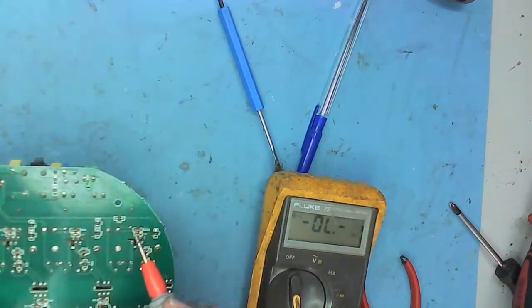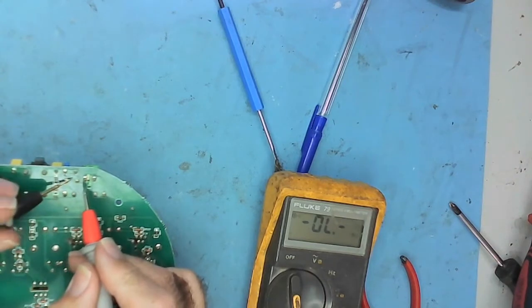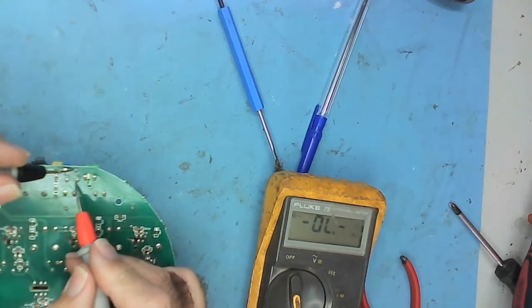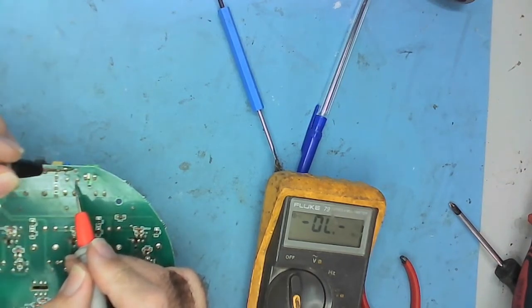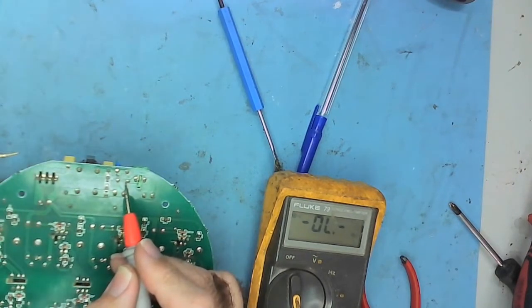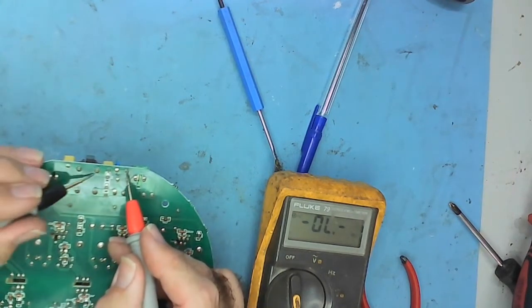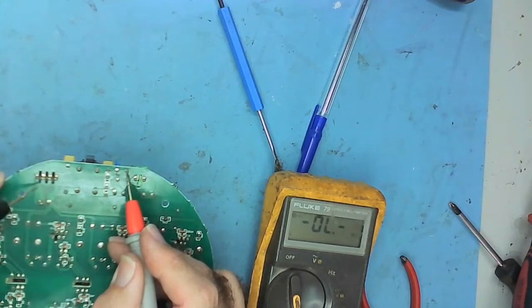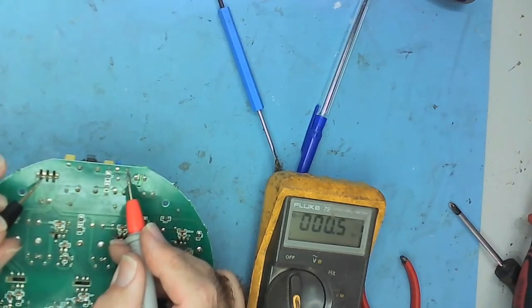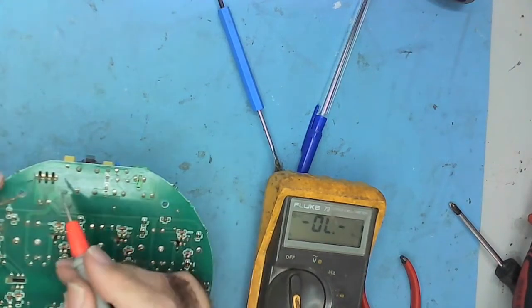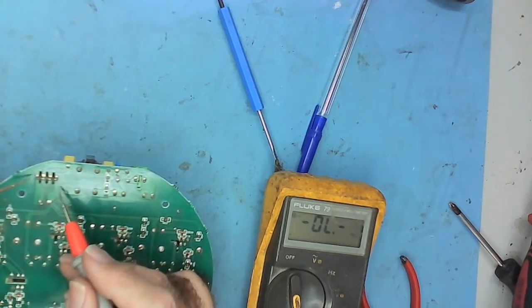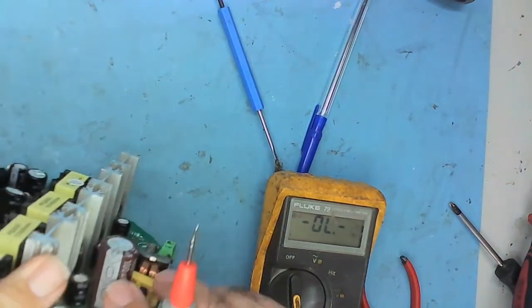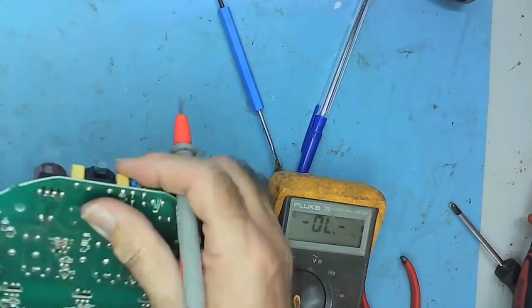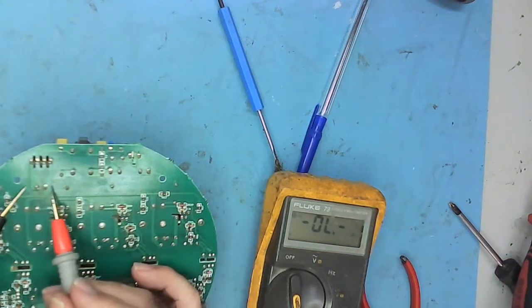So obviously there's no power. This is one end of the thermistor, and that's the other end. But the thermistor's gone, literally. Yeah, it's gone. So other side of the thermistor to the coil, other side of the coil to the other input of the bridge rectifier. So that's how. And then from the other side of here, you've got plus and minus, which go to the capacitor. This end's minus, we can see the minus sign. So the first place we're going to check for short is here.